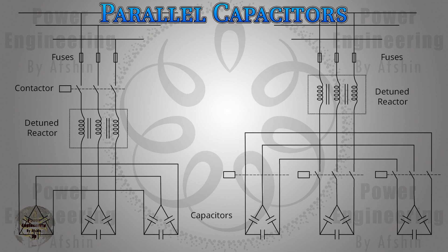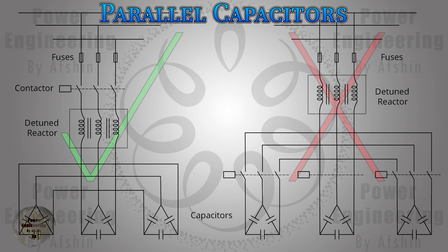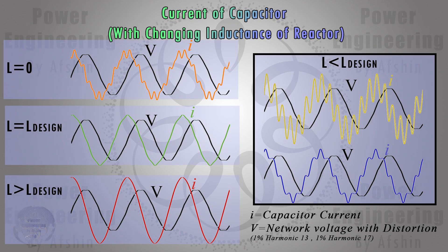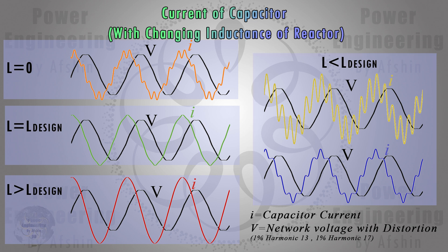For each capacitor connected to a harmonic network, a separate reactor should be used. The only instance where multiple capacitors can be connected to a single reactor is when the capacitors are switched in and out of the circuit simultaneously, based on the current curve shown in the image.